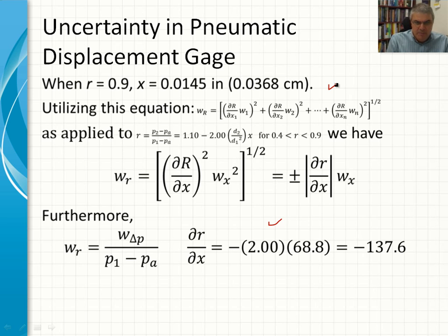We sum them up, and then we take the square root of that sum. It's called the square root of sum of the squares, and it is shown in some books as SRSS. It is, again, as we have seen before, based on statistics, and it would really help to calculate the uncertainty. It would simplify the procedure.